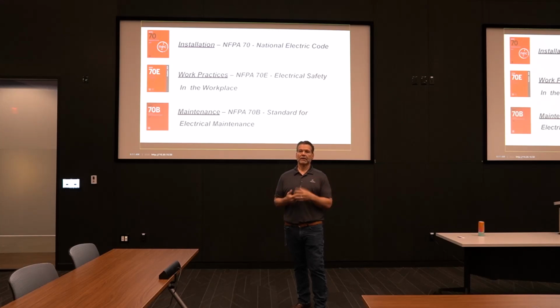is that equipment actually safe? You look at an arc flash label and the incident energy is labeled on there. There are a lot of factors that go into that, and if that equipment is not properly maintained, that arc flash label may no longer be correct. You may have a different available fault current. You may have a different breaker opening time.